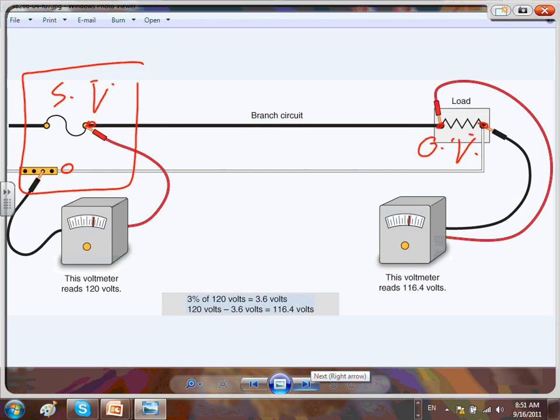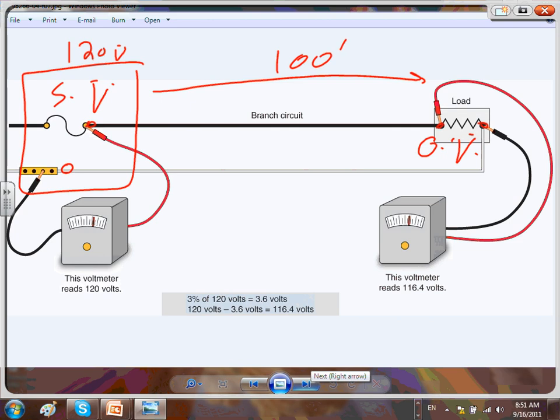This is called the nominal voltage, and this is the operating voltage from here to here. Operating voltage versus system voltage — system voltage is right at the panel. Say I have 120 volts at the panel. Then I move all the way 100 feet. Do you think you're going to find 120 after 100 feet? You're lucky if you have 110 volts. The operating voltage is right at the equipment; the system voltage is right at the panel.